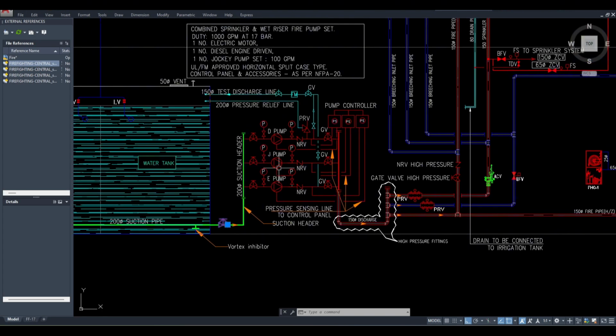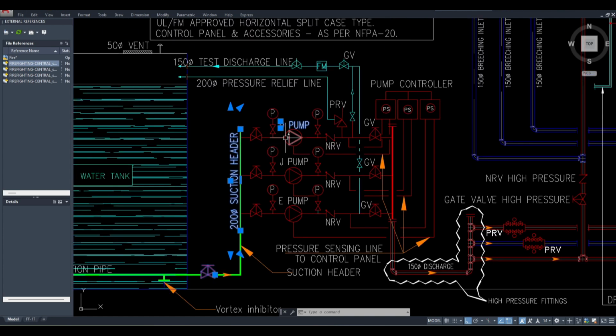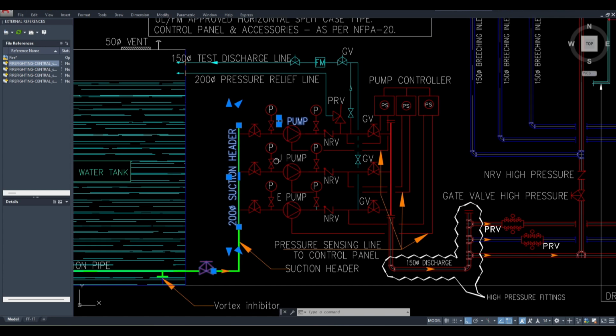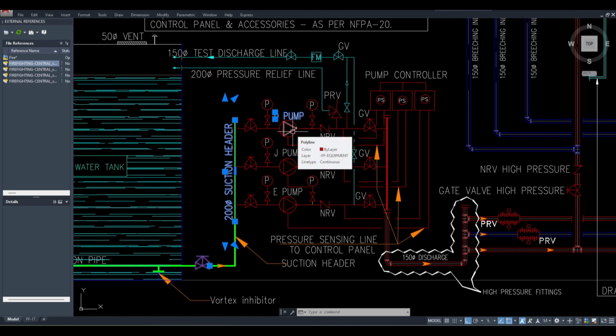Then from this pump to this header, the connection length should be a minimum of 1200 mm. So try to maintain, not just try, it is a must, you need to keep 1.2 meters away between the pump and the header. We will not go into the depth of why this is technically required, just understand that it is required, the minimum requirement you need to know as a coordinator.